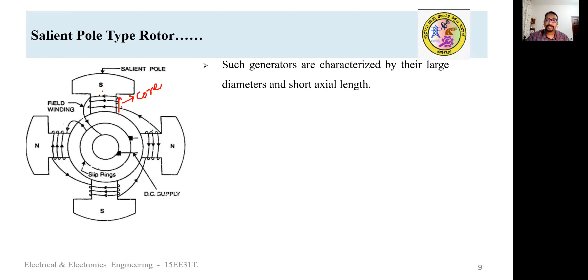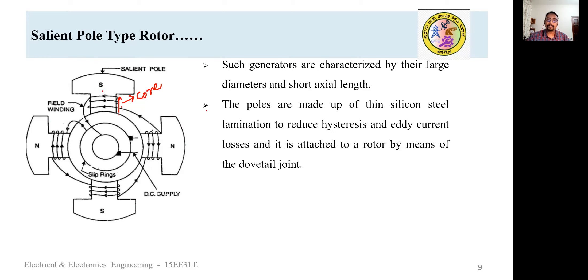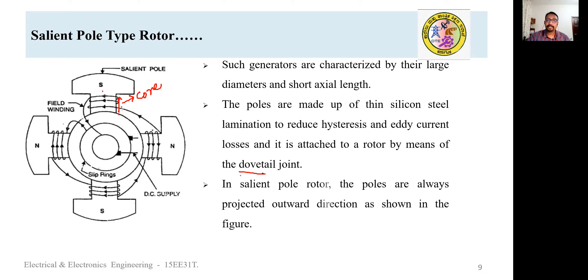Such generators are characterized by their large diameter and short axial length. The poles are made up of thin laminations of silicon steel — silicon steel to reduce hysteresis loss, and thin laminations to reduce eddy current loss. These salient poles are attached to the heavy magnetic drum with the help of a dovetail joint.